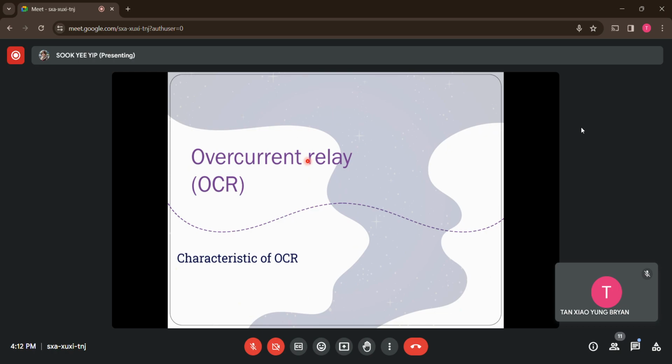Just now we went through the general working description for the fuse and the overcurrent relay. In order to have time coordination for backup protection, let's say we have overcurrent situations, we know that fuses are not suitable, right? That's why we use overcurrent relays. There are two settings we can adjust for an overcurrent relay: the plug setting as well as the time multiplier setting. And we have gone through, if not mistaken, two examples to understand how we can do the setting for the relay, if we are using more than one relay for overcurrent protection.